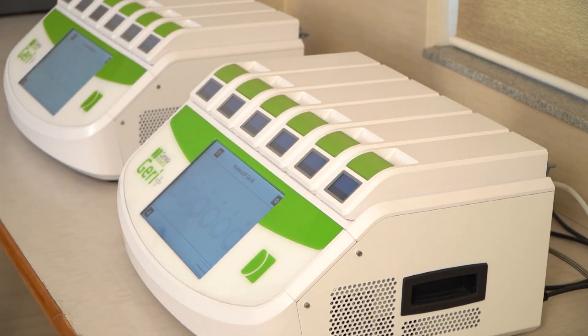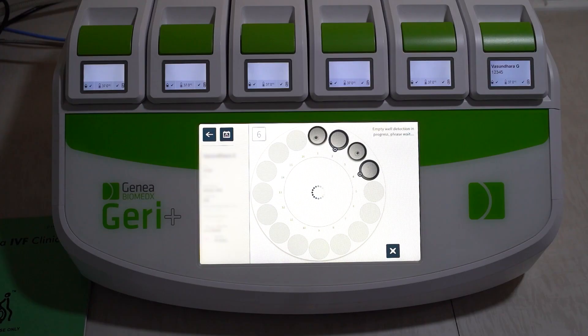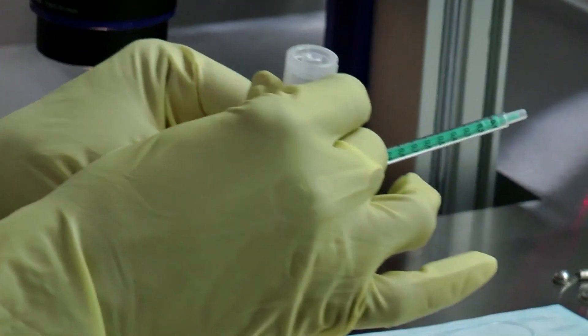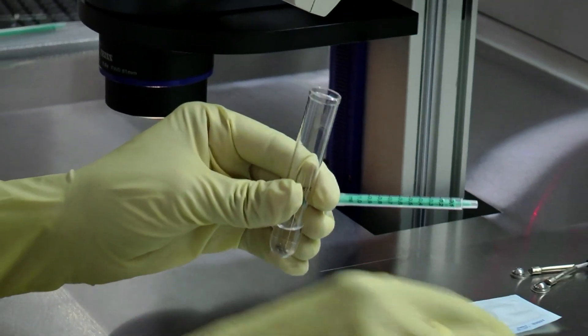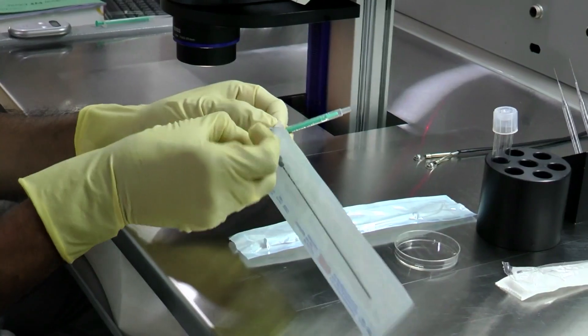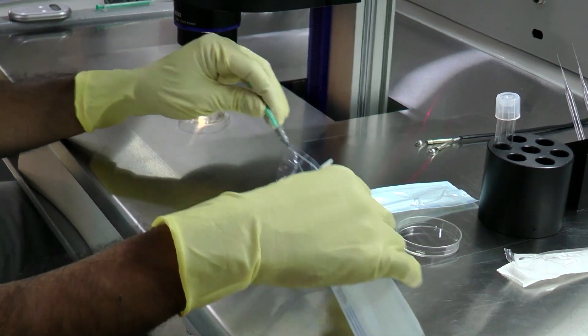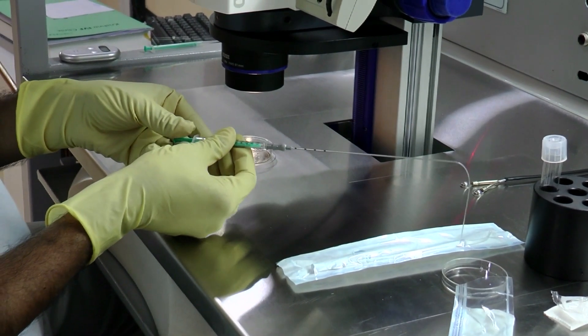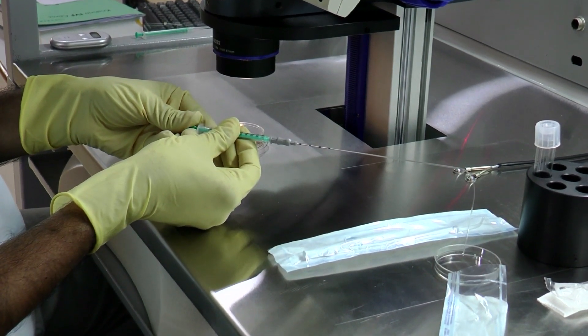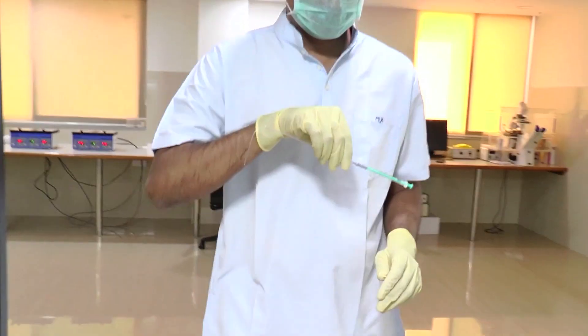Injected eggs are cultured in the embryo system under controlled conditions of temperature, CO2, and environment for four to five days depending on the particular IVF clinical protocol. On the day of embryo transfer, good quality embryos are selected. An embryo transfer syringe filled with transfer medium is connected to an embryo transfer catheter, and the embryos are loaded into the catheter. The catheter loaded with embryos is then handed over to the gynecologist for embryo transfer into the female partner.